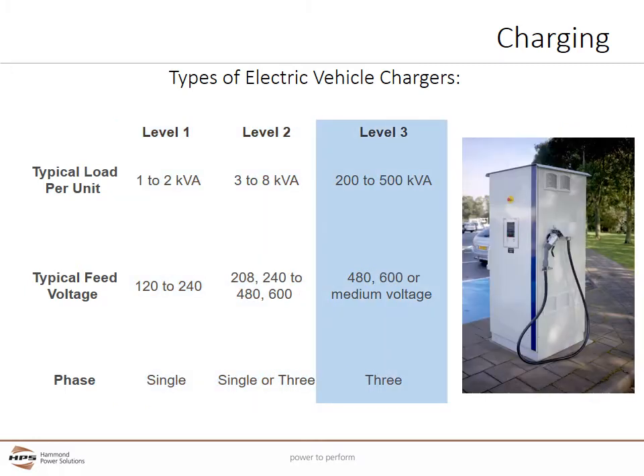Level 3 chargers are essentially large DC power supplies and can supply significantly more power than a vehicle's onboard charger can. Level 3 chargers are usually supplied with 480 volt three-phase sources. Often, the installations are supplied directly with medium voltage power from the utility, which needs to be reduced to 480 volts. Level 3 chargers can supply 50 to 100 miles or more of travel per hour of charge, but are large and costly to install. In the future, Level 4 chargers will be able to supply 170 or more miles of travel per hour of charge. One Level 3 or Level 4 charger can have as much electrical demand as dozens of Level 1 and 2 chargers, typically between 200 and 500 kVA per charging point. Level 3 and Level 4 chargers can cause significant power quality and current surge issues when installed.